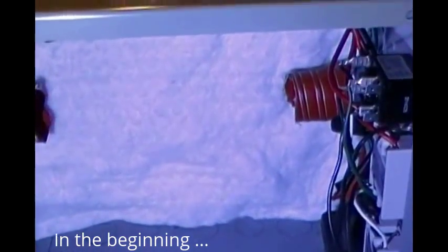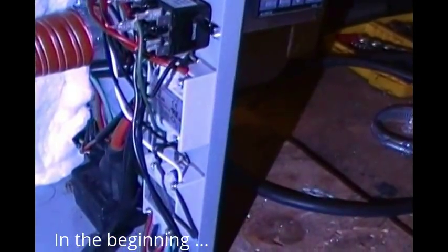To blow heat off of the heat exchanger. What I have this set up as is when the heaters turn off, I have a relay set up in here that recognizes that the PID has told the SSRs to turn the power off to the heating elements.